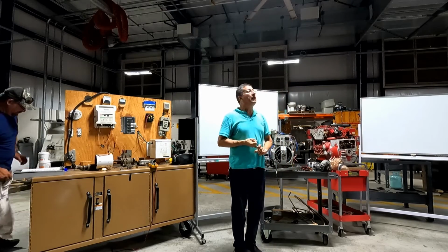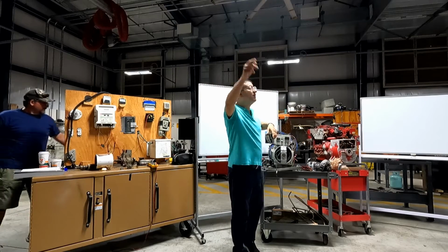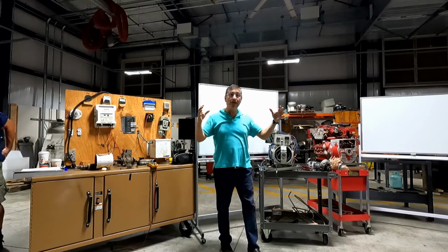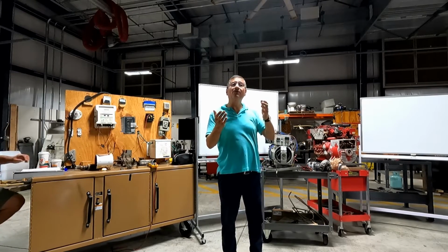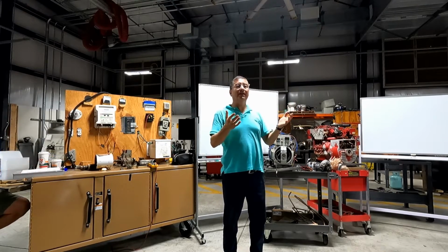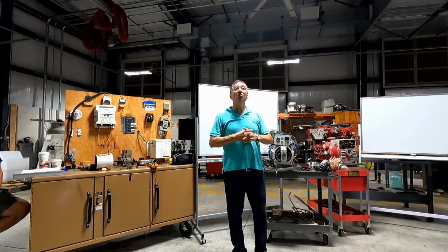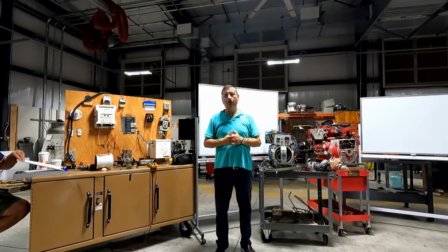It's according to how many loads you have. Oh, I want to install a big refrigerator, 2 air conditioning equipment, 7 fans, lights, this. You add it up, you calculate the total power in kilowatts. And with that power, you convert it to horsepower to calculate the engine of the generator, and you calculate the generator. I'm going to explain the procedure. It's simple, but you need to know how many loads are in my boat, right? Yeah. Okay.